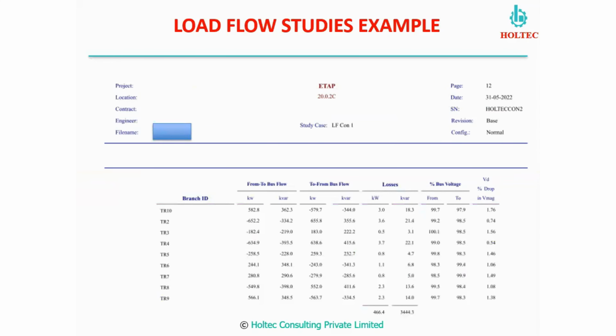This is our ETAP report summary, where we can find the losses, especially the branch losses and the losses in the transformers. So when we go through these parameters, we can see where we have a potential to improve, and accordingly we can take corrective actions in the system, and subsequently we can achieve lesser overall distribution losses. You see in this particular case where we have two cement lines, four power transformers, and about 1 WHR as a source. The total MV distribution losses, not in motors and generators, only in transformers and the branch cables, is coming in the range of 466 kilowatt. So this is huge, which you can save.